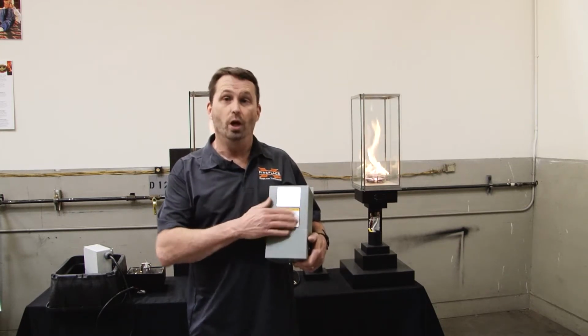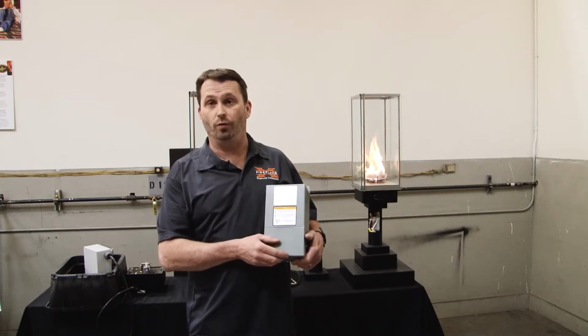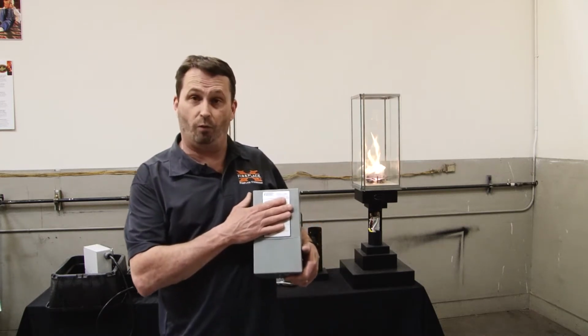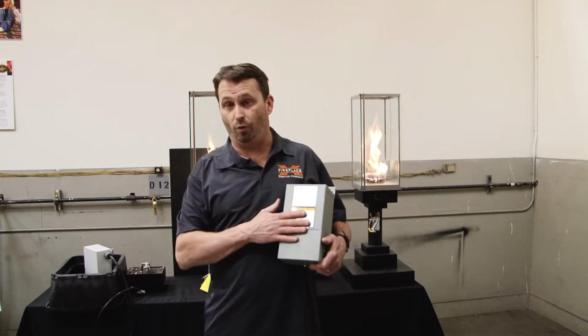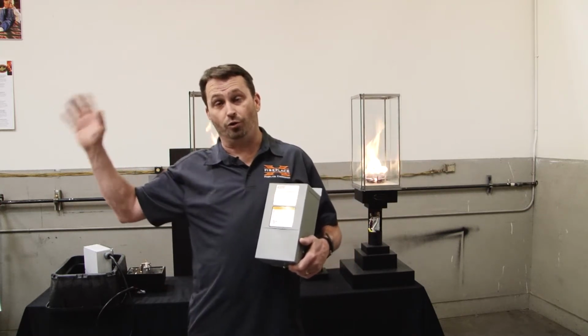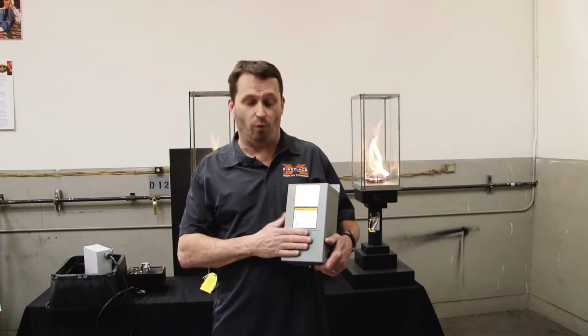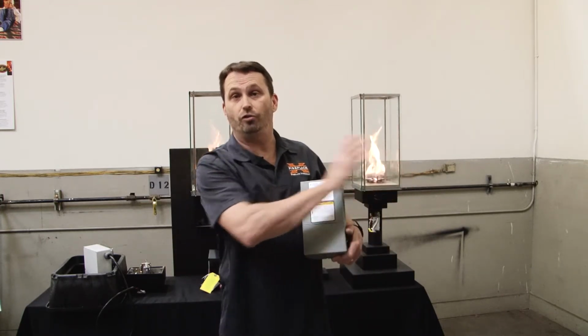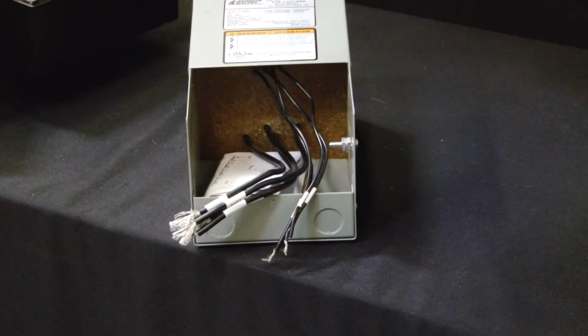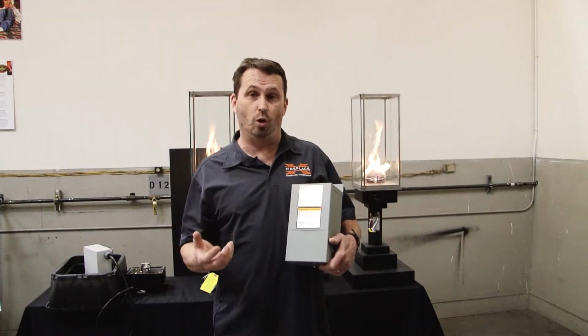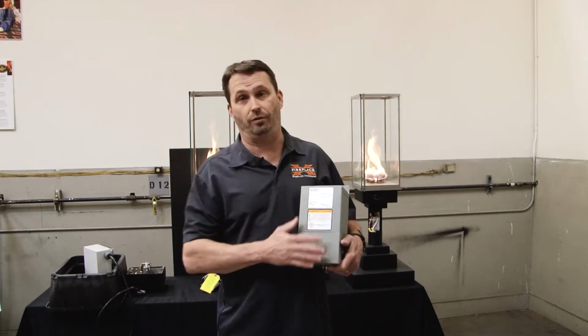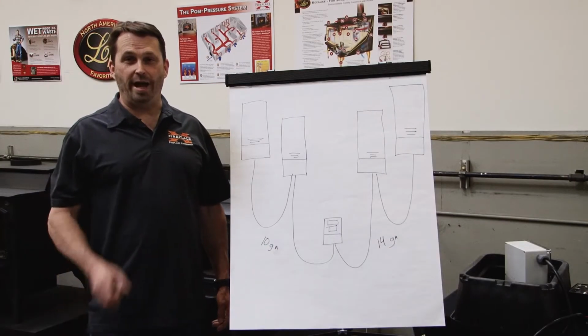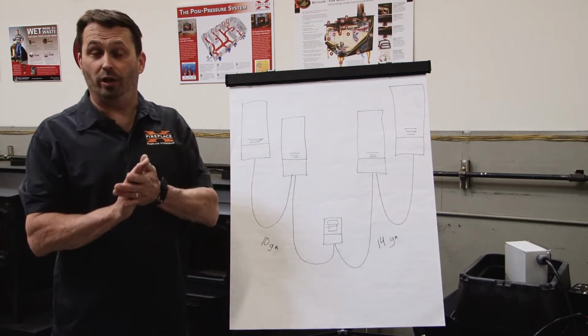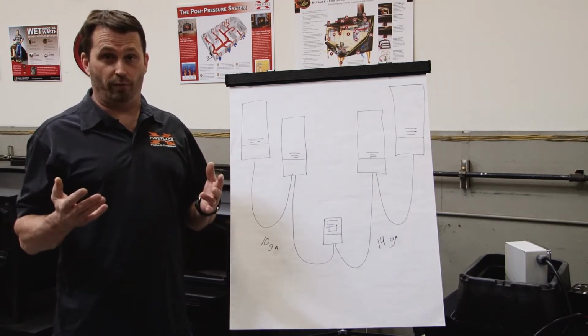From the transformer to the torch, you'll run 24 volt AC service. So this is a 24 volt AC transformer from 110 to 24 volts: from the house or the service panel to the transformer, 110 volts. From the transformer out to the torches, 24 volts AC. This really lets us ease up the installation because there's no high voltage regulation codes that apply to the 24 volts out to the torches. All right, number 2 on the memory list for planning your installation is wiring of the torch.